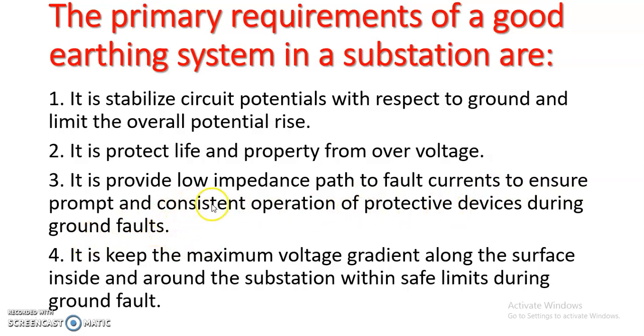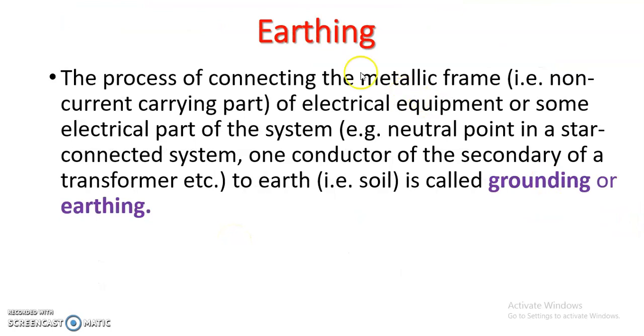If a ground fault occurs, it will provide a low impedance or low resistance path to that fault current, so that the fault current can easily pass to the ground. Then the fourth important point is that it keeps the maximum voltage gradient along the surface inside and around the substation within the safe limit during the ground fault. So these are some primary requirements of a good earthing system. Then we'll see the earthing.